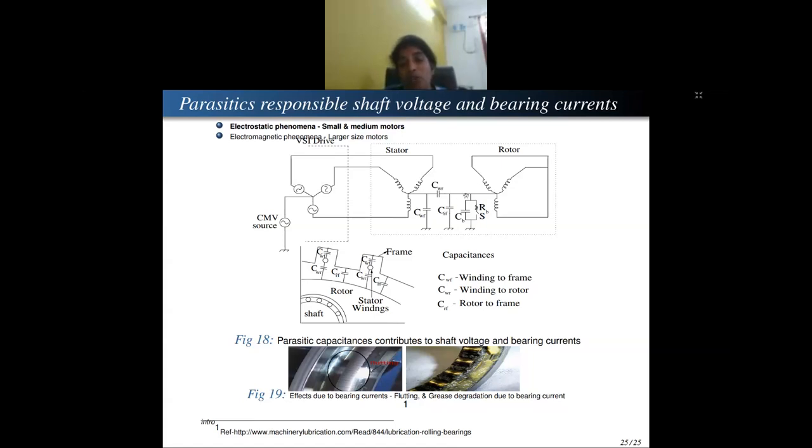Okay, now if you look at the capacitor CRF, across this your bearing would be there. You can model this bearing like a nonlinear switch with insulation. Whenever this voltage exceeds the lubrication breakdown of the bearing, you will see a current called electric discharge machining current. It is like our capacitive current suddenly discharged at one moment, an impulsive moment.